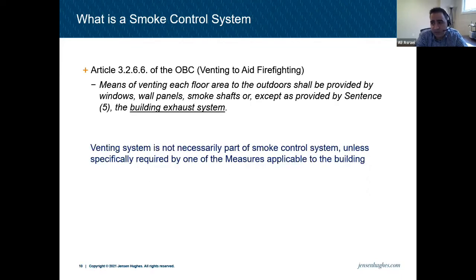And there is Article 3.2.6.6 of the OBC. It's venting to aid firefighting, a means of venting each floor area to outdoors. It's either by windows, wall panels, a smoke shaft, or, if the building is sprinklered, you can use your mechanical system, basically those exhaust fans you see in garages. That's for venting to aid firefighting. This is not necessarily part of a smoke control system unless it is one of the measures that we're using. For example, when we get there, Measure F uses this, and that becomes part of your smoke control system, but normally it's not considered part of the smoke control system. It's good practice to include it, by the way. We can talk about it later on.